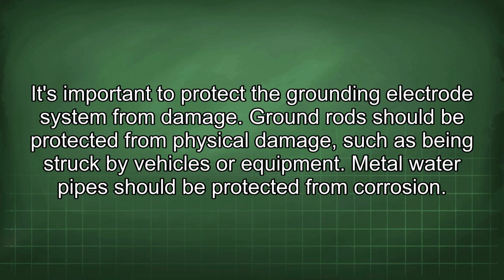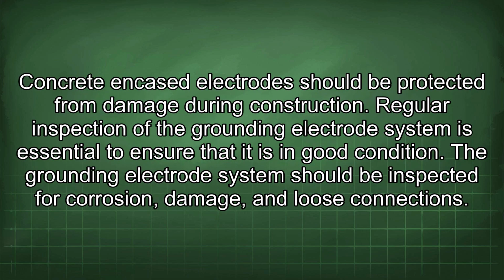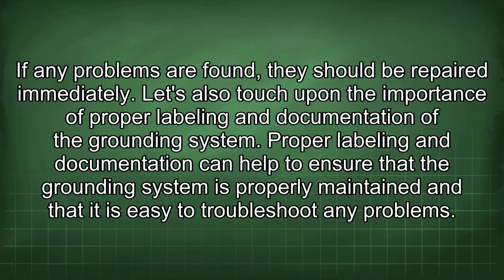It's important to protect the grounding electrode system from damage. Ground rods should be protected from physical damage, such as being struck by vehicles or equipment. Metal water pipes should be protected from corrosion. Concrete encased electrodes should be protected from damage during construction. Regular inspection of the grounding electrode system is essential to ensure that it is in good condition. The grounding electrode system should be inspected for corrosion, damage, and loose connections. If any problems are found, they should be repaired immediately.